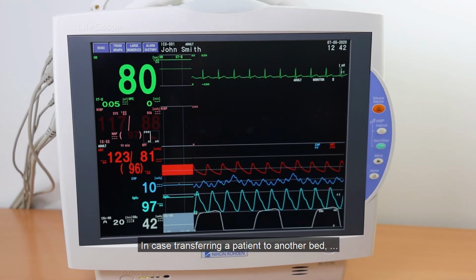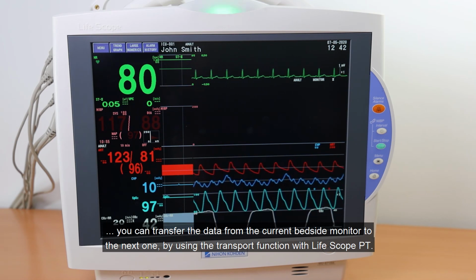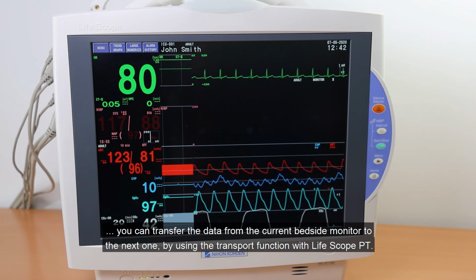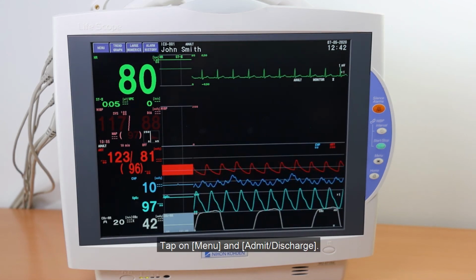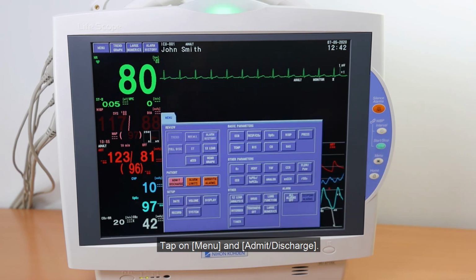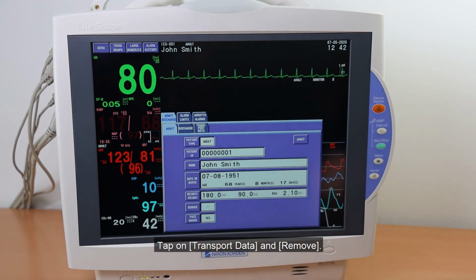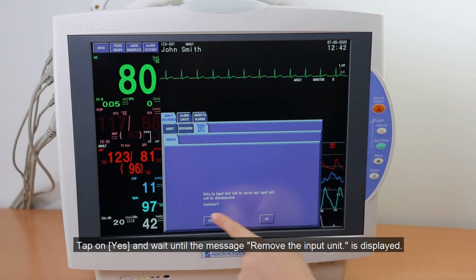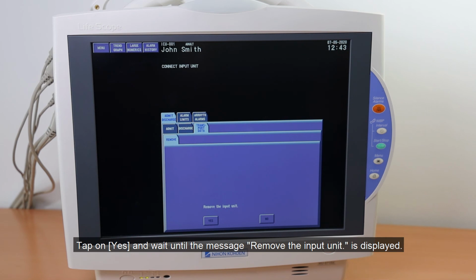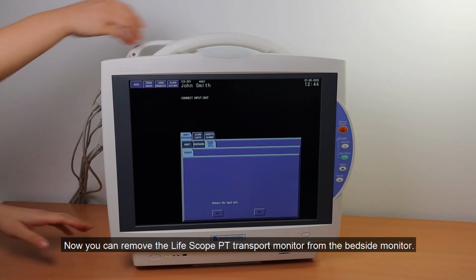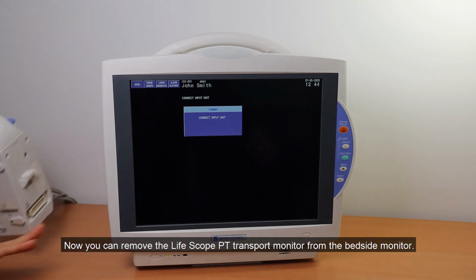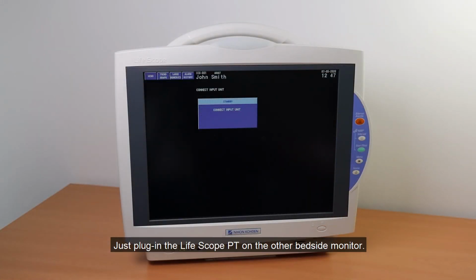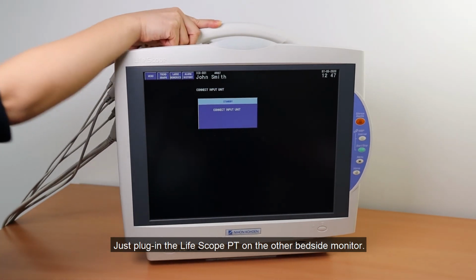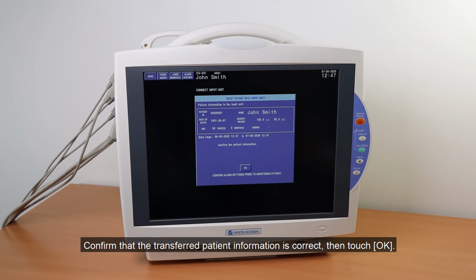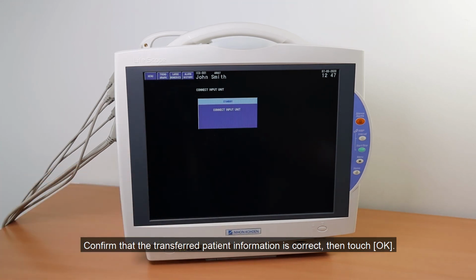In case of transferring a patient to another bed, you can transfer the data from the current bedside monitor to the next one by using Transport function with LifeScope PT. Tap on Menu and Admit Discharge. Tap on Transport Data and Remove. Tap Yes and wait until the message Remove the input unit is displayed. Now you can remove the LifeScope PT transport monitor from the bedside monitor. Just plug in the LifeScope PT on the other bedside monitor. Confirm that the transferred patient information is correct, and then touch OK.